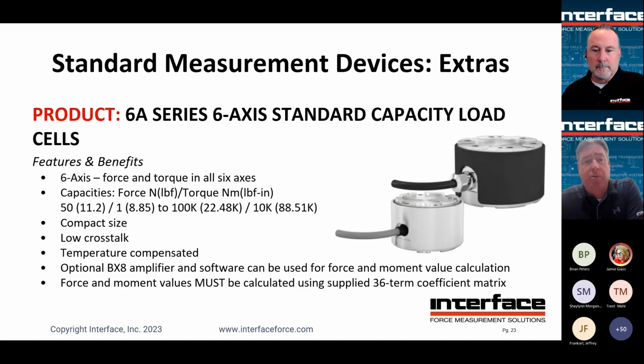6-axis load cells, this is the step up from the 3-axis product. This measures X, Y, and Z and the moments about each. Pretty broad range of force, relatively compact for all the different axes that they take. Low crosstalk. These work a little bit differently than a standard load cell in that they do not have a dedicated bridge output for each axis.